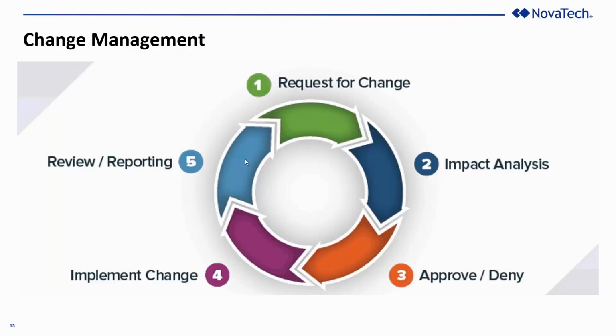In our example, the comms personnel would submit a request for change to say that they would like to swap out the switch and when. The impact analysis might look at the requested time, know that communications with the substation would be lost, and check whether there are any switching programs or similar planned work at that substation involving SCADA that might be interfered with if the change went ahead.